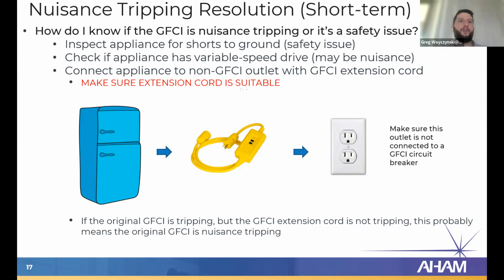And then you can just do a little test and see if that original GFCI is tripping, but the GFCI extension cord that you've now replaced that original GFCI with is not tripping. That probably means that that original GFCI breaker is nuisance tripping. That probably means there's nothing wrong with the appliance and that GFCI breaker is tripping when it shouldn't. So that's a quick test that you can do.